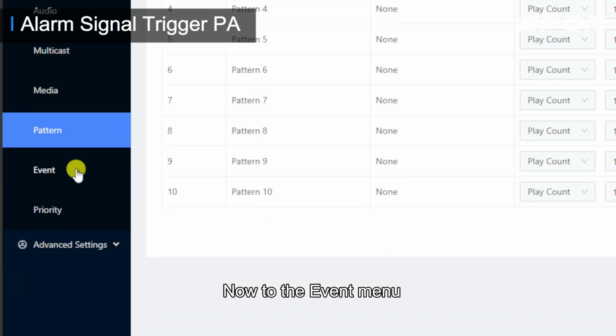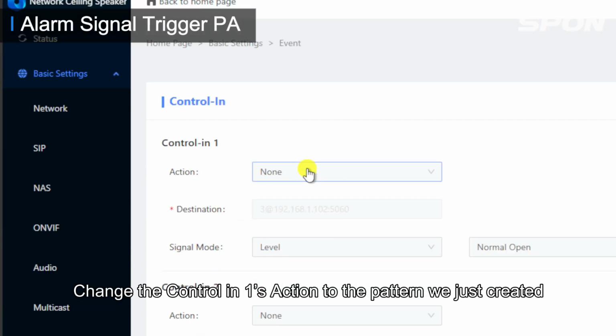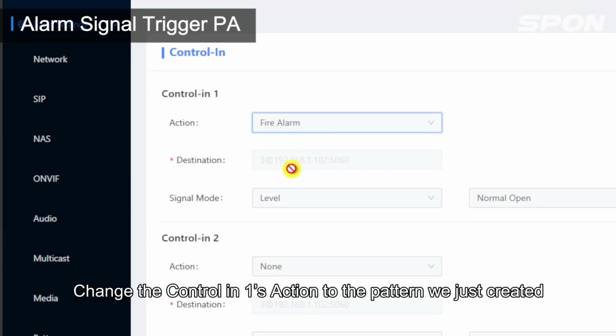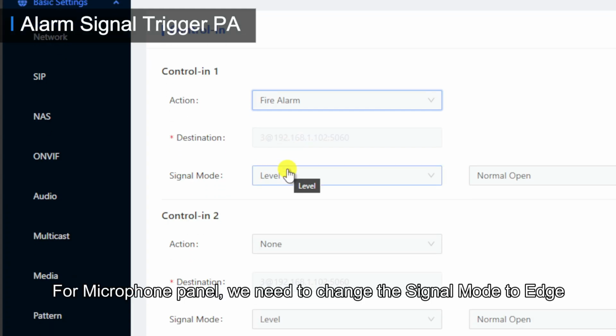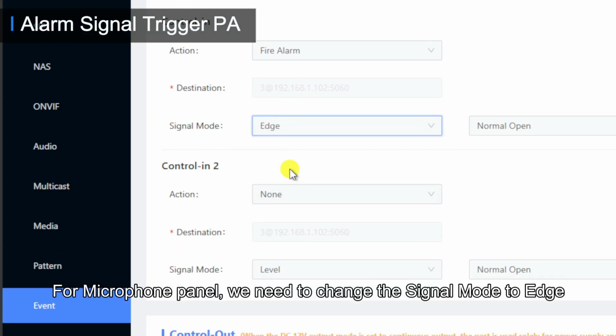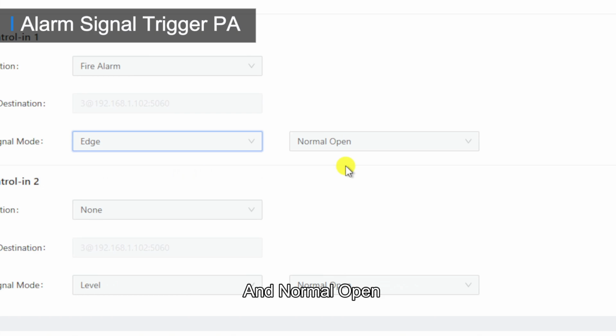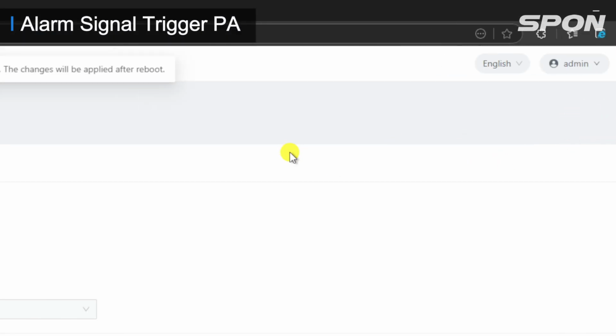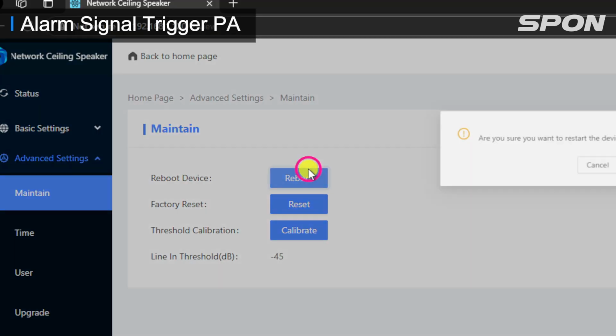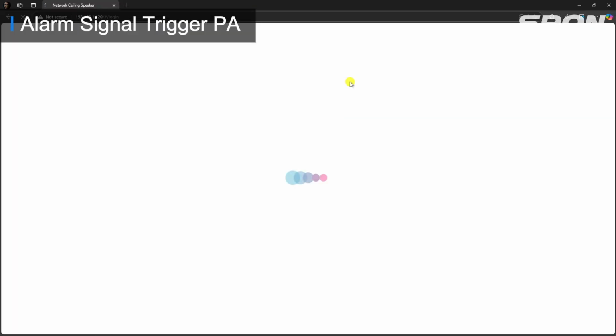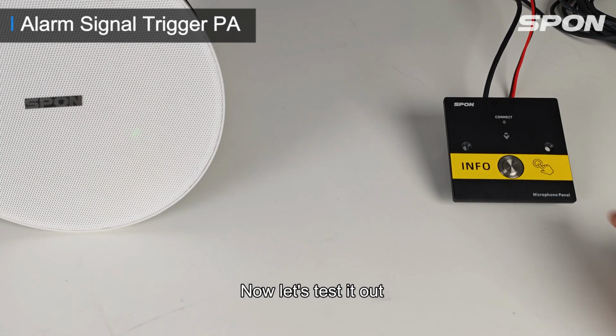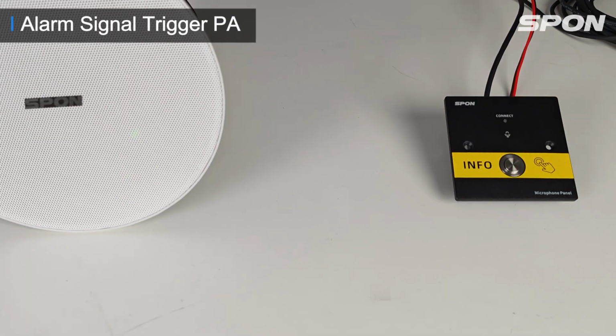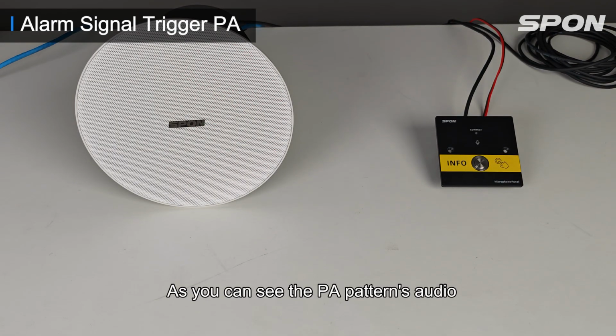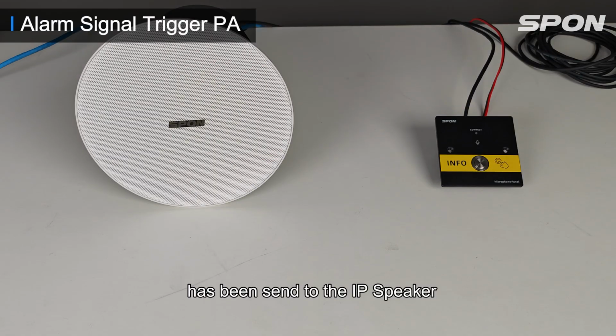Now go to the event menu. Change control in one's action to the pattern we just created. For the microphone panel, we need to change the signal mode to edge and normal open. Save and restart. Now let's test it out. As you can see, the PA pattern's audio has been sent to the IP speaker.